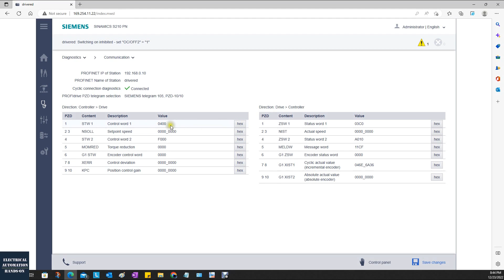If the motor is running, the motor will transfer the status to the PLC. Okay, this is very useful. If you wonder why I sent the command but the servo drive cannot spin, cannot power up, then in some cases you can monitor the bit or the command word from this screen, for commissioning and for troubleshooting purposes. So this is the diagnostic.